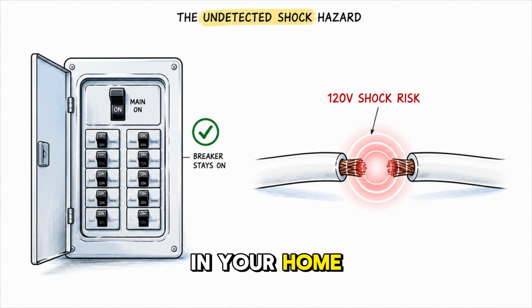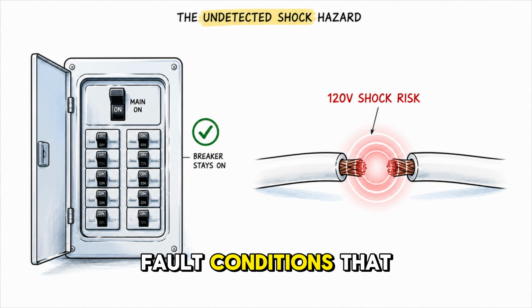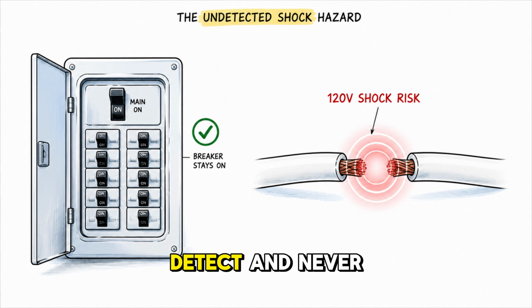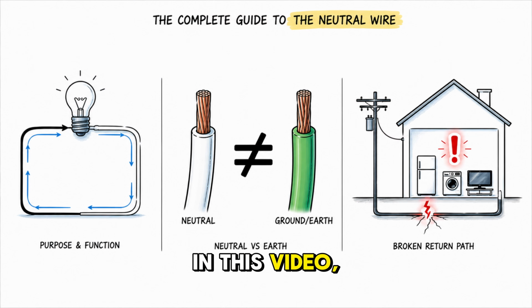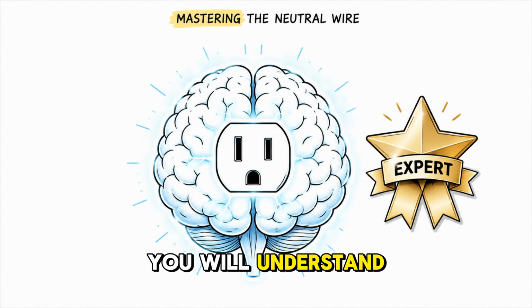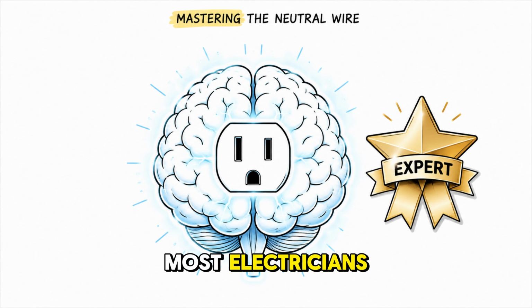The neutral wire in your home carries 120 volts of potential shock risk under certain fault conditions that your circuit breaker will never detect and never stop. In this video, we are going to cover everything about the neutral wire. Why does it exist? What it does every second of every day. Why it looks identical to the earth wire but is completely different. Why touching it can kill you if the return path is broken. And what happens to every appliance in your home the moment it breaks. By the end of this video, you will understand the neutral wire better than most electricians.